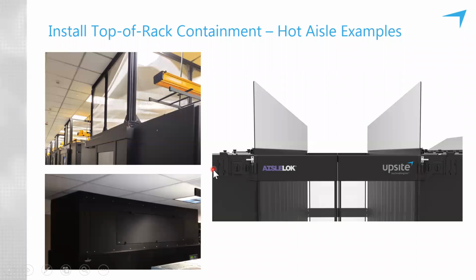Okay, thanks, Lars. So we're going to move to some similar examples, but just for hot aisle containment this time. You heard me earlier talk about hot aisle containment being a vertical perimeter built around the hot aisle from the tops of the racks to a ceiling. Hot aisle containment is most times used where you've got an overhead return plenum above a drop ceiling. That's the case in the photo in the top left. And there are going to be perforated register tiles in the ceiling instead of the solid tiles that you're typically familiar with and see here.